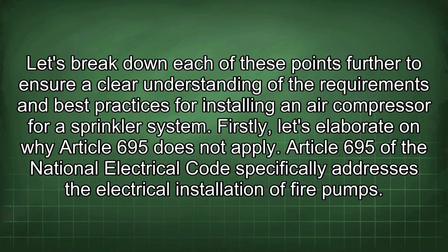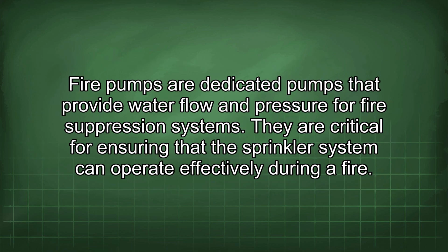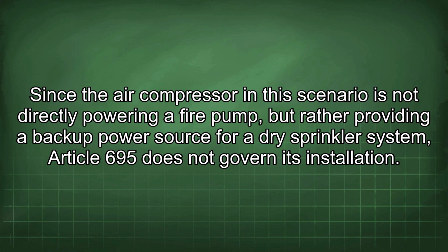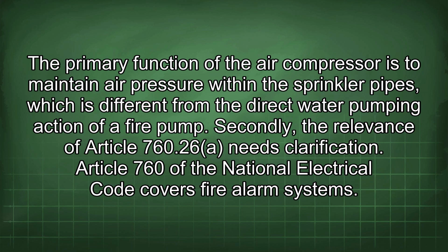Firstly, let's elaborate on why Article 695 does not apply. Article 695 of the National Electrical Code specifically addresses the electrical installation of fire pumps. Fire pumps are dedicated pumps that provide water flow and pressure for fire suppression systems. They are critical for ensuring that the sprinkler system can operate effectively during a fire. Since the air compressor in this scenario is not directly powering a fire pump, but rather providing a backup power source for a dry sprinkler system, Article 695 does not govern its installation. The primary function of the air compressor is to maintain air pressure within the sprinkler pipes, which is different from the direct water pumping action of a fire pump.